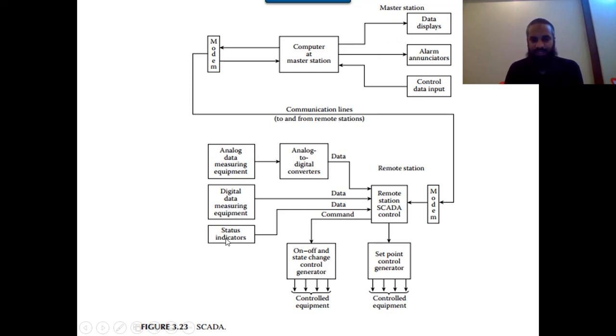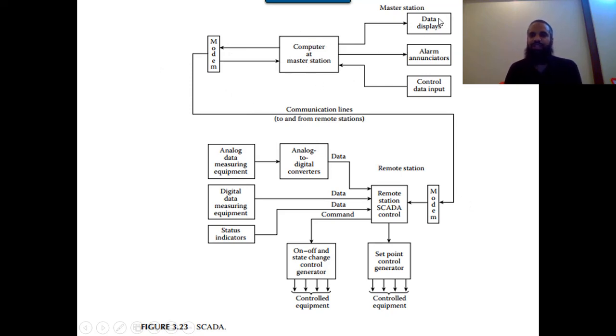The block diagram of the SCADA system shows analog or digital sensors feeding information to the Remote Terminal Unit (RTU). From the RTU, a modem receives and sends information to the master station or central control. Between the master station and remote station, a modem facilitates communication — alternatively a wireless link can be used. From the central control system, there are three kinds of outputs: data display, alarms, and control, which are used to manage all parameters of the remote station.